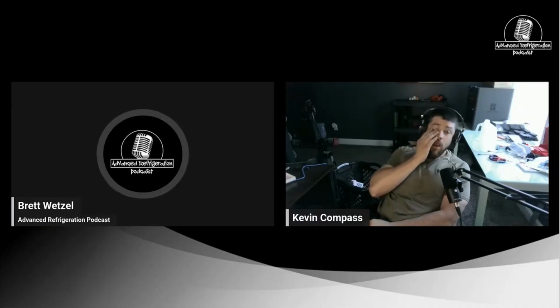All right, I have a question. Someone called me the other day and said, "Hey, I want to change out this iPro to this other iPro. It's the same vintage." And I said, "Yeah, you just need to change the address in the iPro so it communicates." He asked, "How do I do that?" I said, "The Visiograph." He said, "What is that?" Dude, Hill has not been sending Visiographs out with racks. Yeah, that's what he said, and I'm like, "What? What do you do?" So the default address in there is 1 at 9600 baud. Since the iPro is generally on a dedicated comm loop with itself, it's usually address 1 on there.